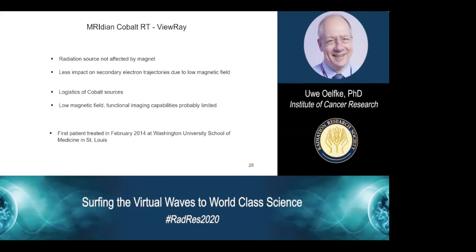What are the pros and cons of this cobalt system? Of course, it was very clever to have a radiation source which is not affected by the magnet. So one of the main problems, the integration of the linear accelerator with the MRI scanner, the most problematic aspects were simply avoided. Then also the lower magnetic field strength of 0.35 Tesla seems to have less impact on the electrons which are produced in radiation therapy within the patient and also within dosimeters. And we will talk about this in the third part of this presentation.